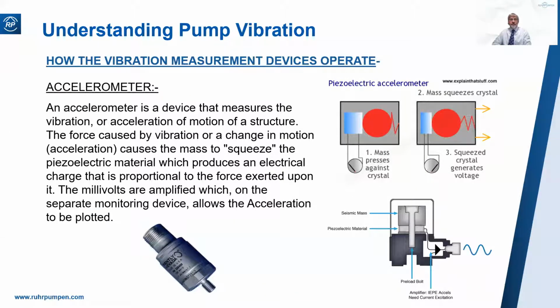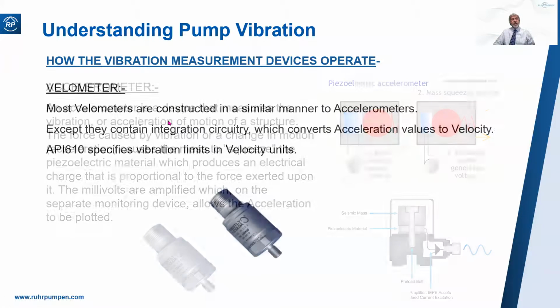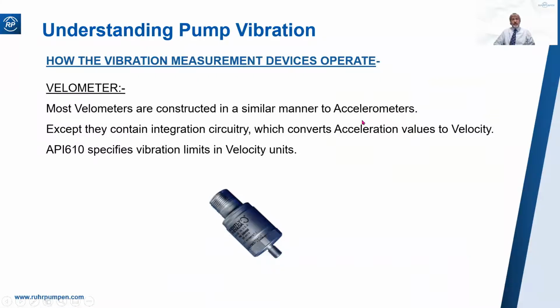This shows simplistically how an accelerometer works. Vibrations on the pump bearing housing cause the mass inside the accelerometer to squeeze the piezoelectric material, it's a mouthful, which produces an electrical charge proportional to the force exerted, so proportional to the vibration. That's an accelerometer. A velometer, generally they are the same as accelerometers, but they contain integration circuitry, which converts acceleration to velocity. And API 610 specifies vibration limits in velocity units.